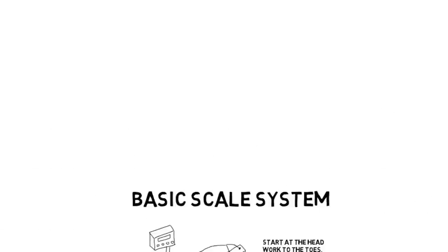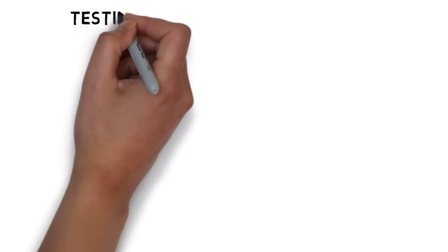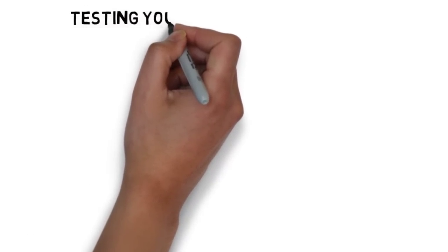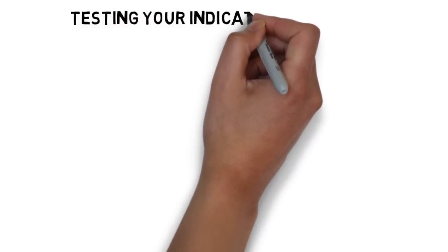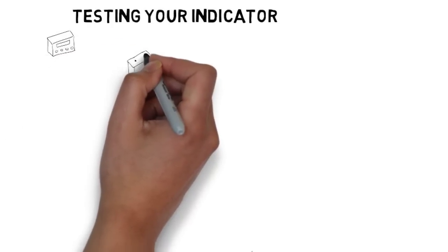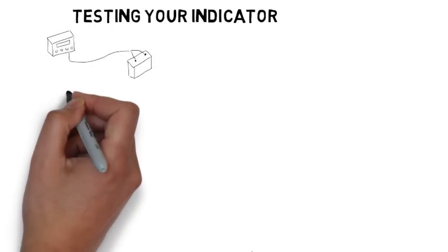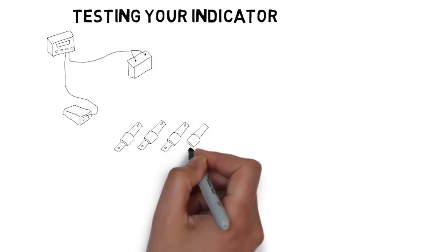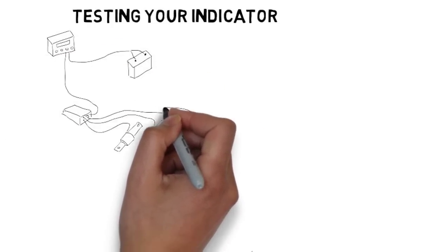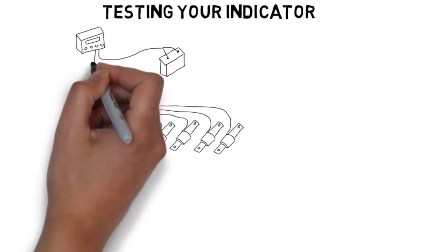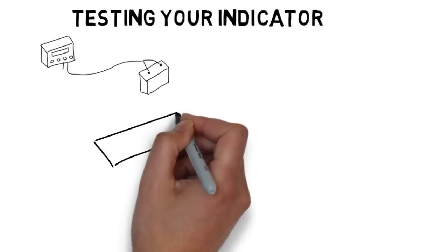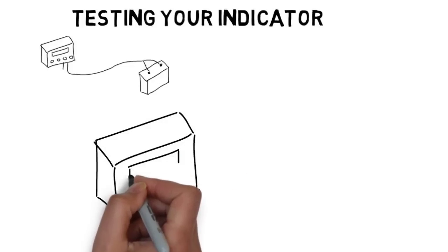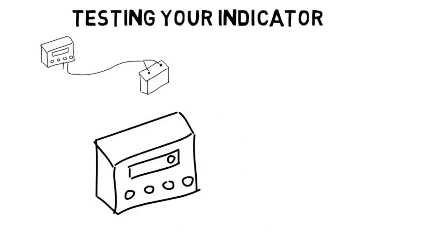After we ensure your indicator is powered correctly, the next thing we want to ensure is the indicator is working properly. You don't really need any fancy simulators or devices to ensure your indicator is working correctly. You can simply unplug the junction box cable from the load cell port and zero your indicator.